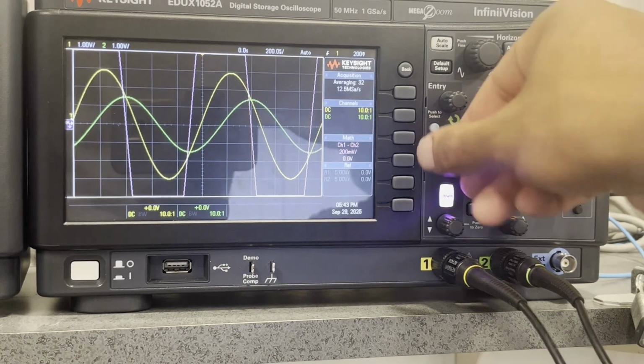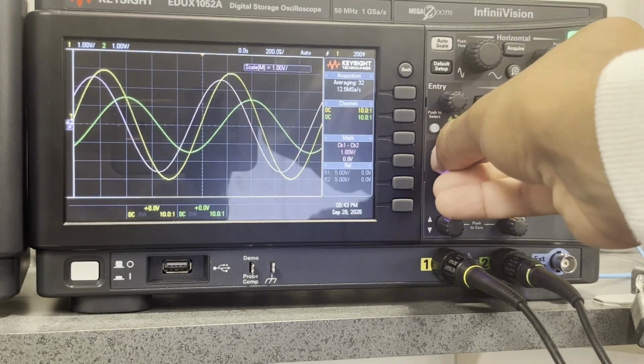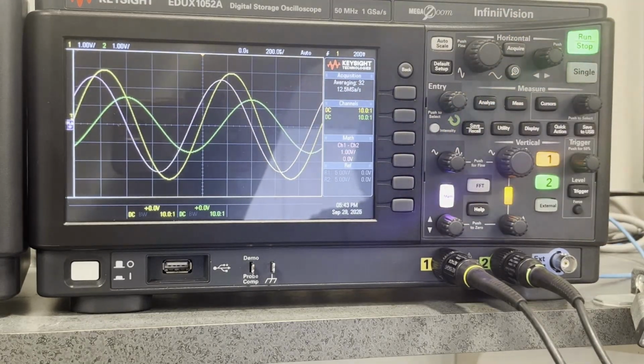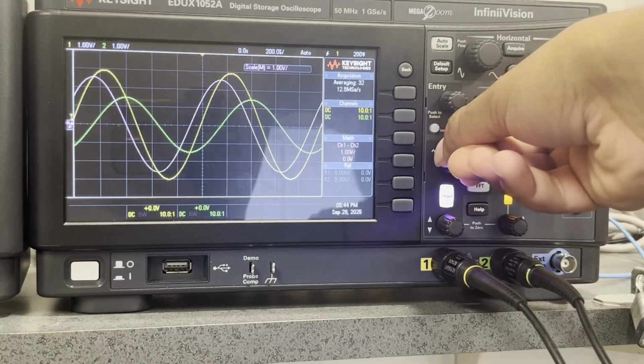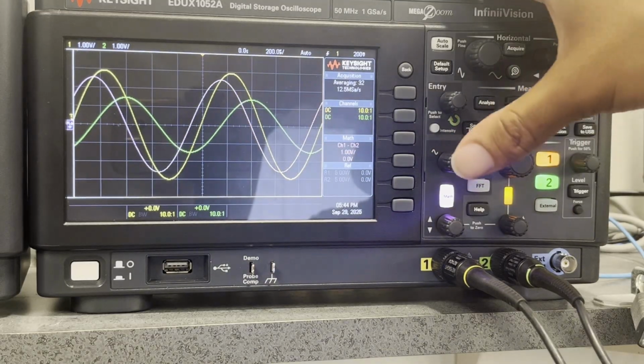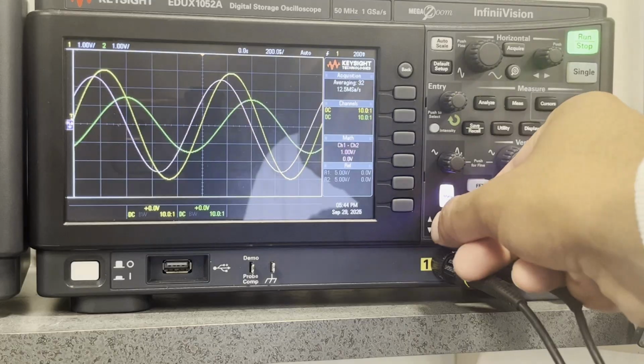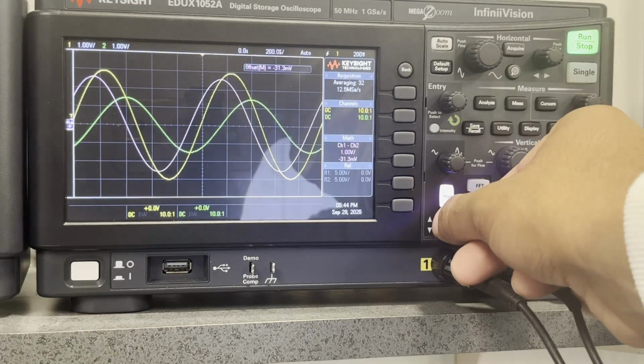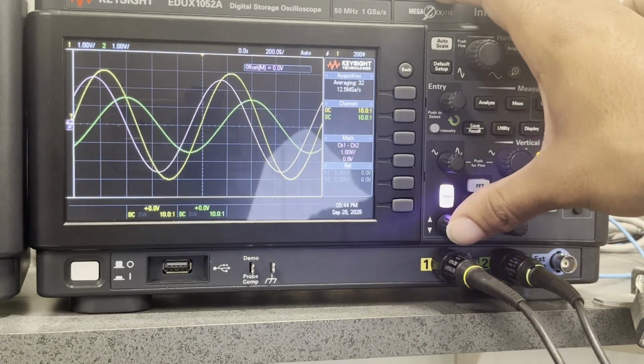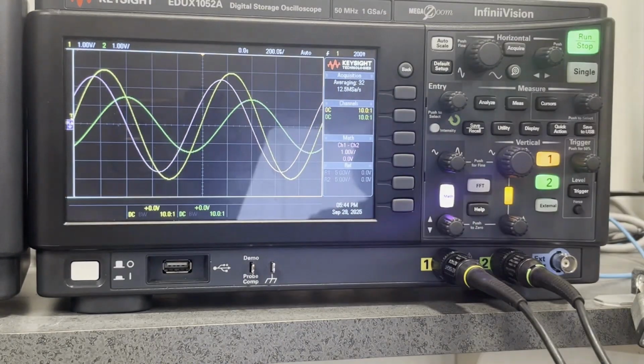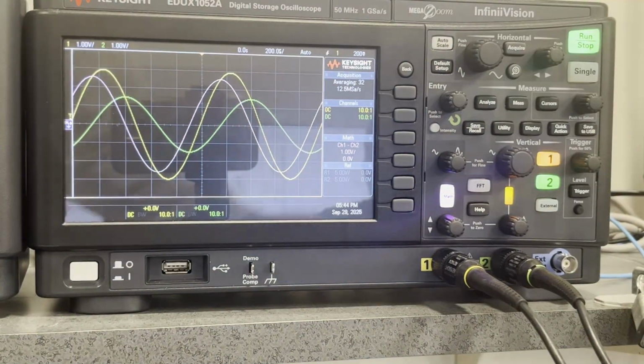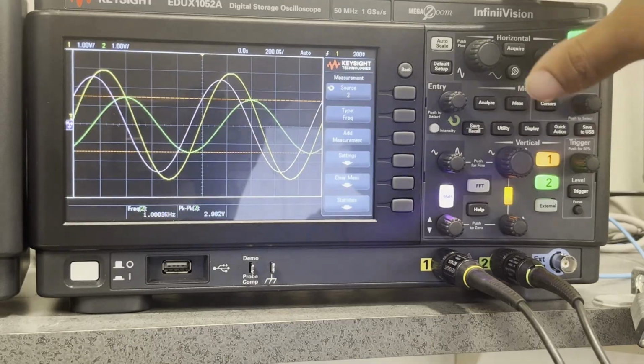The scale can be adjusted using the knob right above the Math button. I've set it to the same as the vertical scale for channel 1 and channel 2. The knob right below the Math button can shift the vertical offset. Just as before, let's make sure our signal is centered at 0 by pressing in on the knob. You can also use the measurement function on the Math channel. Let's try adding a peak-to-peak measurement on the Math channel.